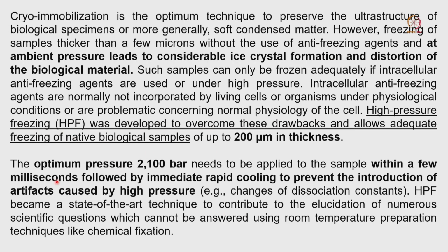How does it work? Generally we use a very high pressure, 2100 bar, that needs to be applied to the sample within a very few milliseconds, followed by immediate rapid cooling to prevent the introduction of artifacts caused by the high pressure. So, we create a very high pressure, 2100 bar, for a very small amount of time, a very few milliseconds, and try to freeze it immediately.